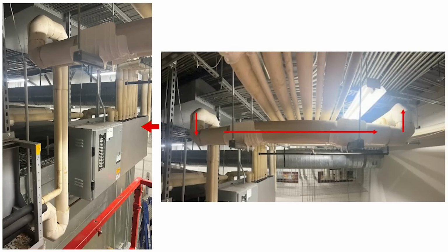Yeah, so from a very basic standpoint, if somebody says, traps, I know about that, it's where you take your drain line... We're talking about refrigerant traps here, right. And we're literally just saying anywhere that it goes down and then back up, at least the diameter of the pipe. That's technically a trap at that point. Exactly right. If we cross the diameter of that pipe with a vertical climb, and we're coming down and then going back up, that line is going to fill up with oil on the suction side, where I have vapor. My vapor has to bring that oil back to my compressor. It's going to do that through velocity.